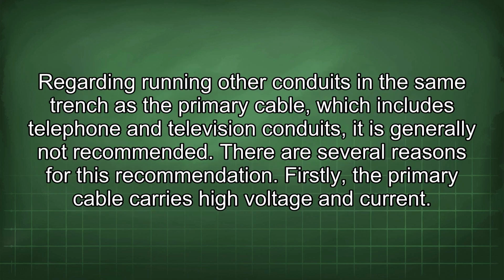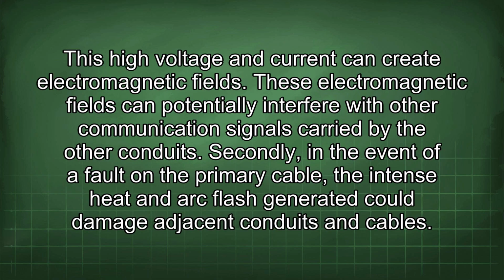Regarding running other conduits in the same trench as the primary cable, which includes telephone and television conduits, it is generally not recommended. There are several reasons for this recommendation. Firstly, the primary cable carries high voltage and current. This high voltage and current can create electromagnetic fields. These electromagnetic fields can potentially interfere with other communication signals carried by the other conduits.